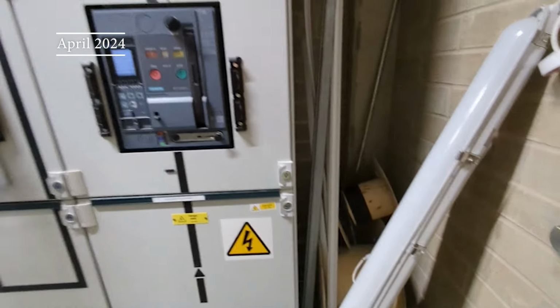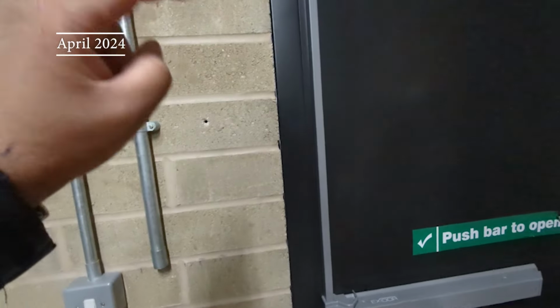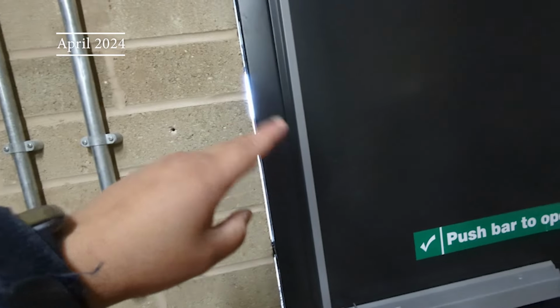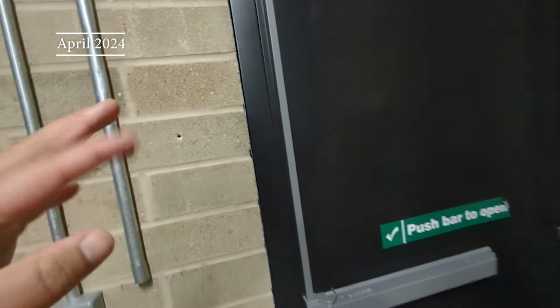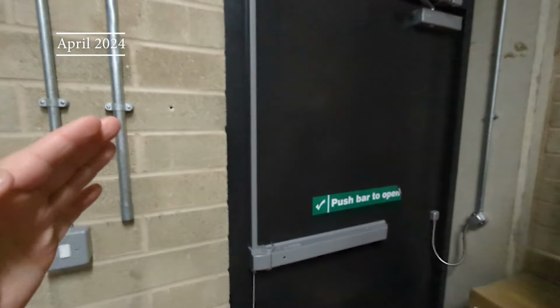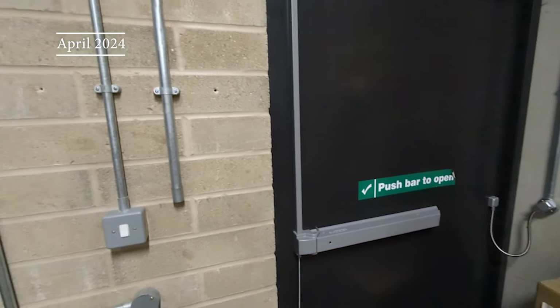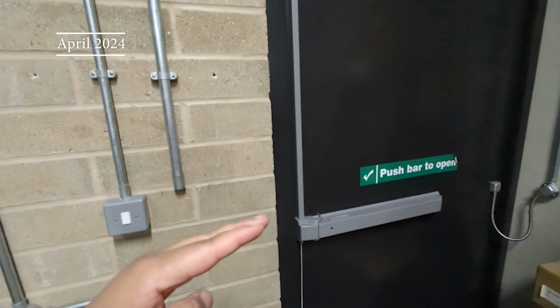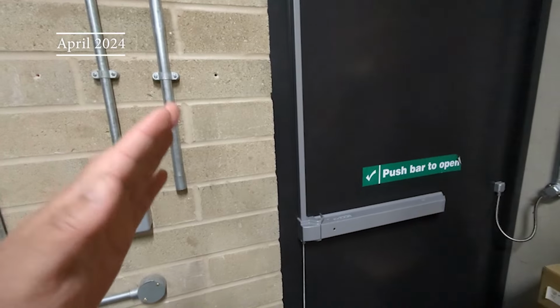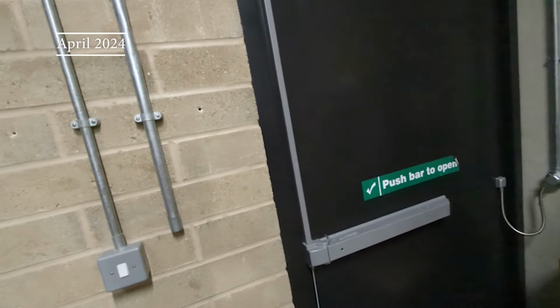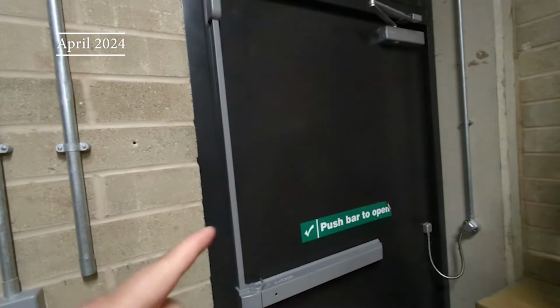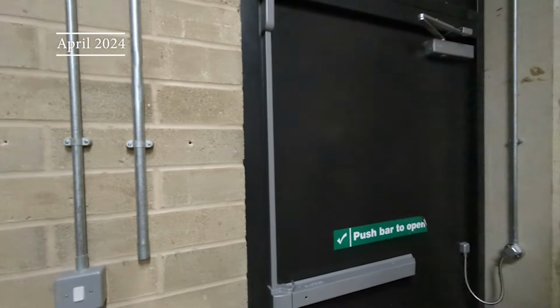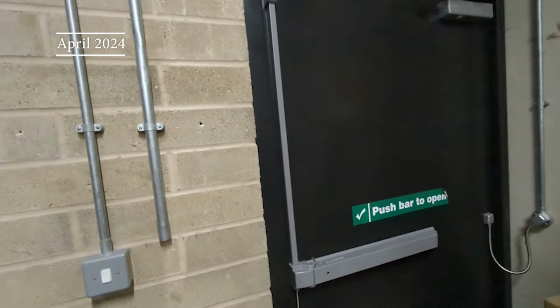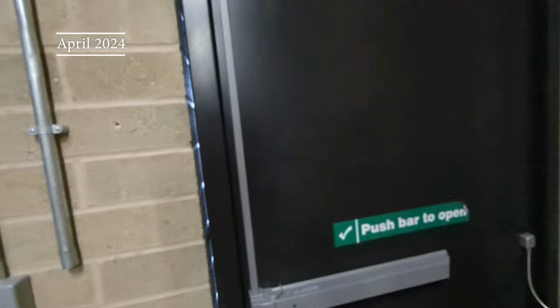So what's happening to me at the moment is that I'm tripping the circuit breakers on those two transformers. I'm getting about 50 amps when I'm lifting a bridge on full angle at full speed. So I've got all of my pumps on full speed, going as fast as they can, and I'm tripping the transformer circuit breaker out there. Then I've got to call the engineer that owns the transformers to come out. That takes him 2 hours to come over here and reset the breaker.